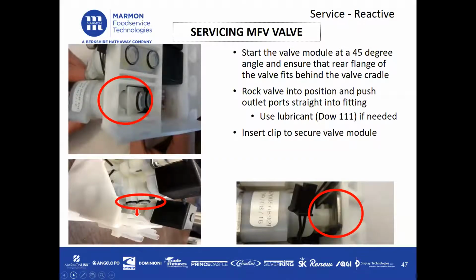Once you put that valve module body back into the valve cradle, you want to put it on a 45-degree angle, so you make sure this flat side of the valve module actually goes in first. Then you're going to rock the module back into these ports here, as you can see. And you want to make sure that these O-rings are lubricated, as you don't want these O-rings to be pinched or damaged as you're pushing it back into the ports. To secure this valve module back onto the valve cradle, you want to make sure that you reinsert the clip to keep it secured onto the valve cradle.